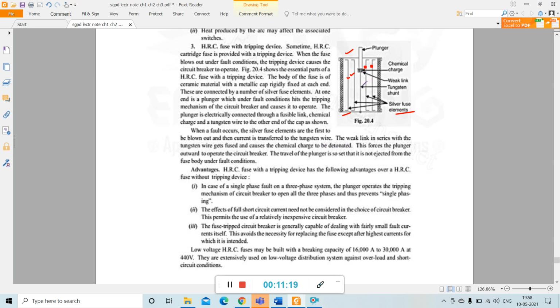So when current shifts to this tungsten wire, the weak link in series with the tungsten wire fuses and causes the chemical charge to be detonated. That means there is an activation of the chemical charge, and this forces the plunger outward to operate the circuit breaker. The travel of the plunger is set so that it is not ejected from the fuse body under fault condition. So what are the advantages of this type of fuse?